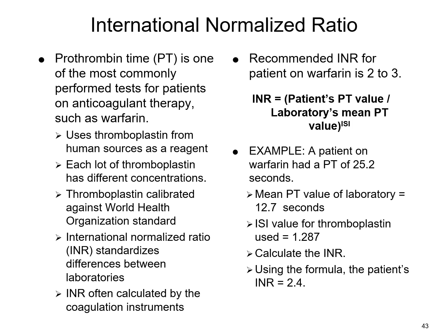The main thing that you've got to remember is that when you get a new lot of reagents, you're going to have to verify what that ISI is and make sure that you put that in the proper place when you're adding that new reagent. If you do not, and there's a big variation, you could be causing a lot of complications for your patients as well as your physicians who are trying to treat these patients.